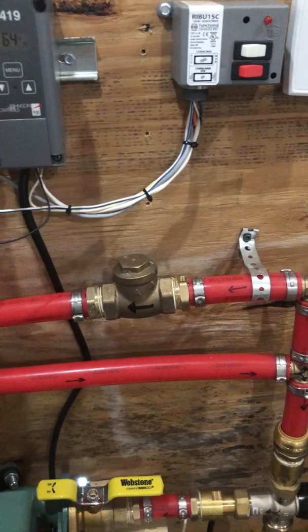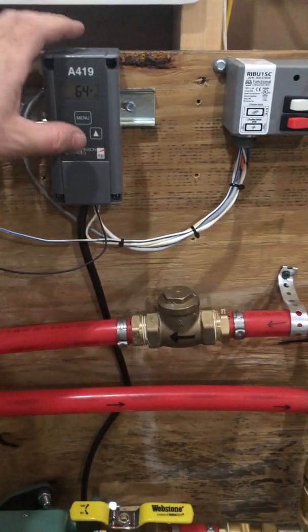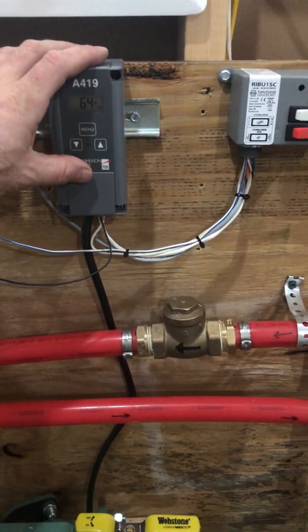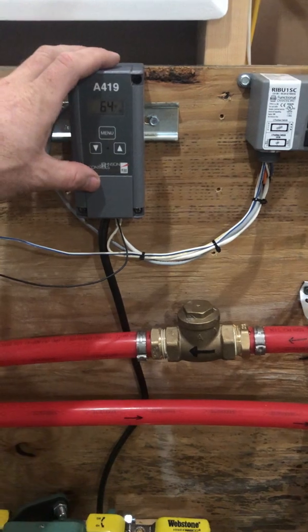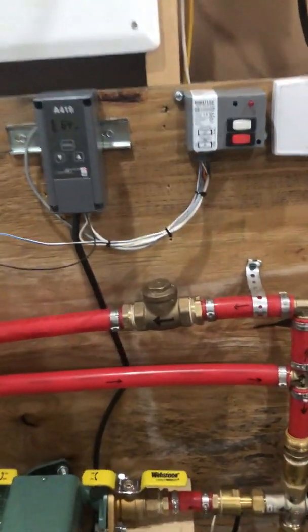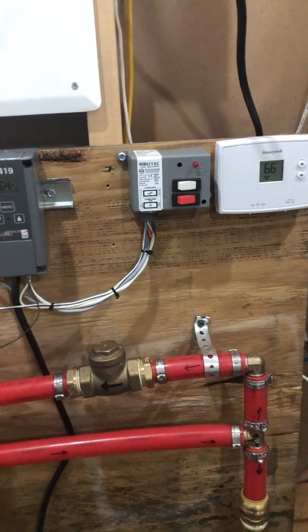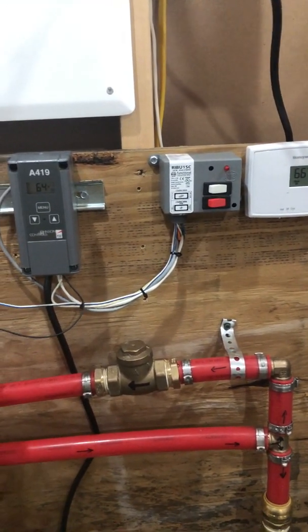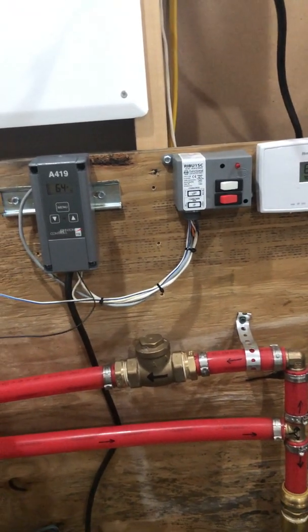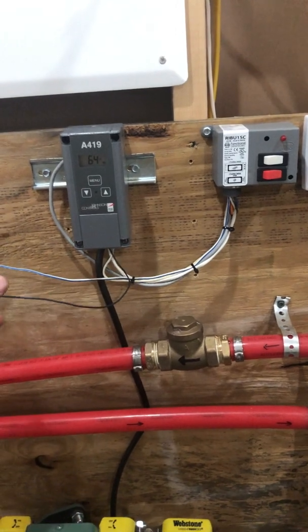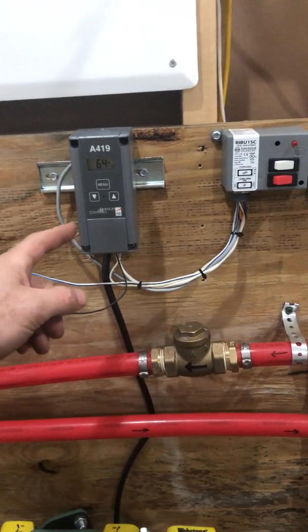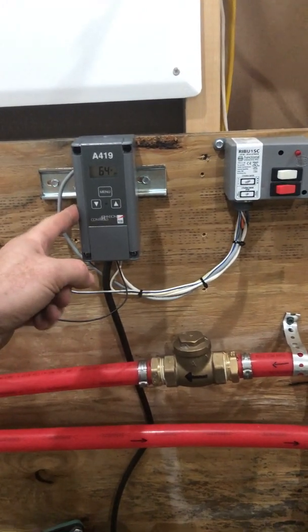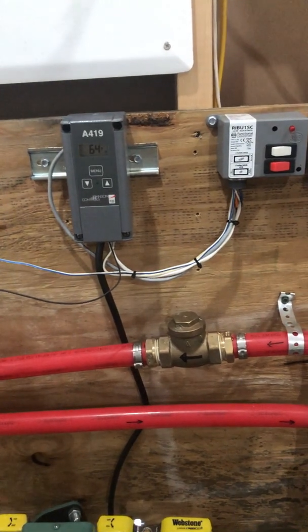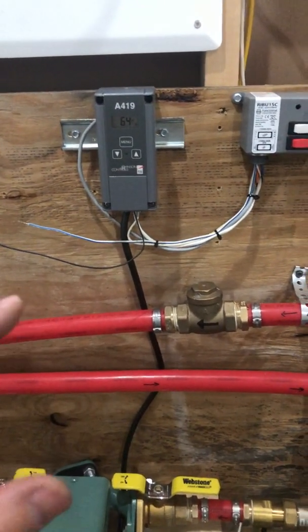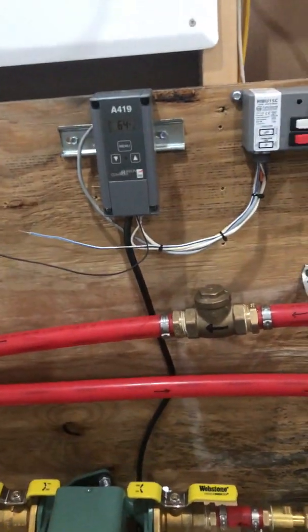So I've got two of these aquastats, and again, this one actually controls the relays, and it will just send a 24-volt signal to the air handler. When that happens, it's saying, if the water temperature is over 100 degrees, it's going to disable my outdoor heat pump and I don't have to use electricity. In the event that I don't feed the boiler and I go out of town or whatever happens, this senses the water temperature dropping below 100, my heat pump will kick on like normal, and my main circulation pump will still continue to circulate, so I won't have to worry about any freezing issues.